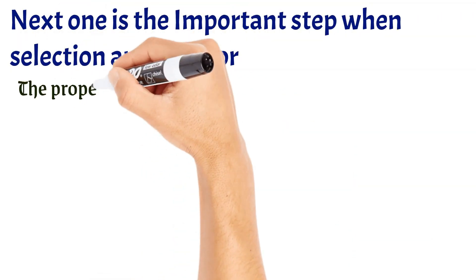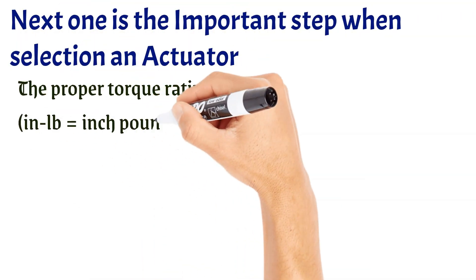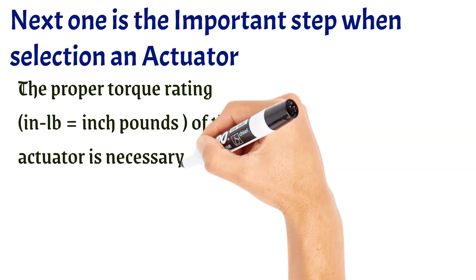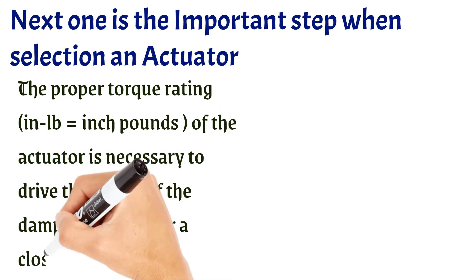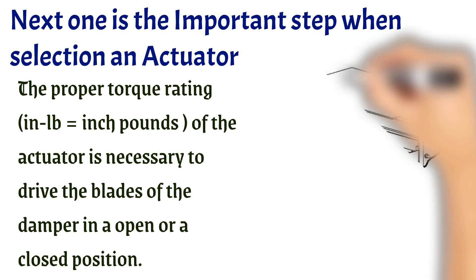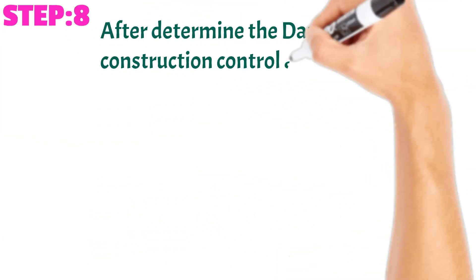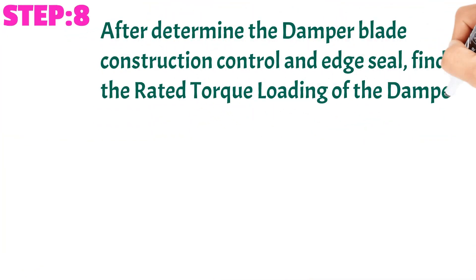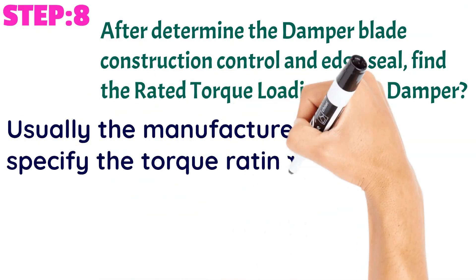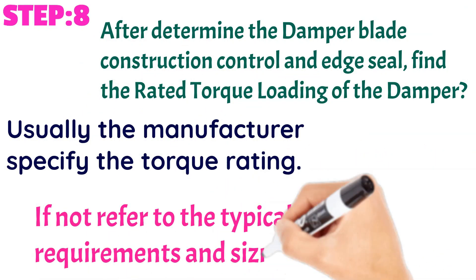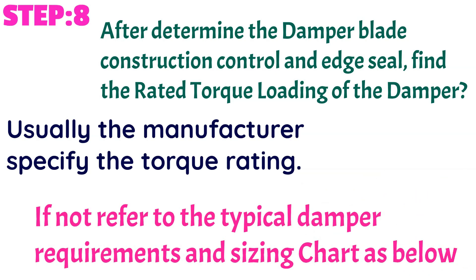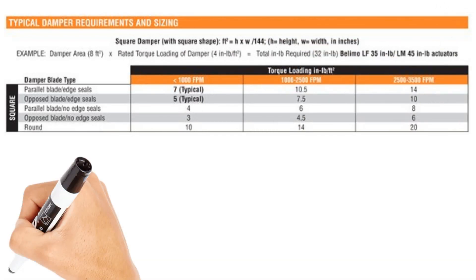The next important step when selecting an actuator is the proper torque rating of the actuator, which is necessary to drive the blades of the damper in an open or closed position. Step number eight: After determining the damper blade construction and edge seal, find the rated torque loading of the damper. Usually the manufacturer specifies the torque rating. If not, refer to the typical damper requirements and sizing chart below.